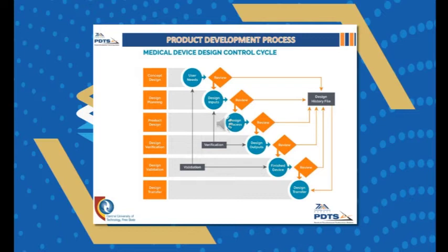It is very important to translate the user needs into design inputs. You need to make sure that the product you came up with meets the requirements defined in the beginning. This is a regulatory requirement for medical device development. You need to confirm that the design output meets the design input. This process is called design verification.